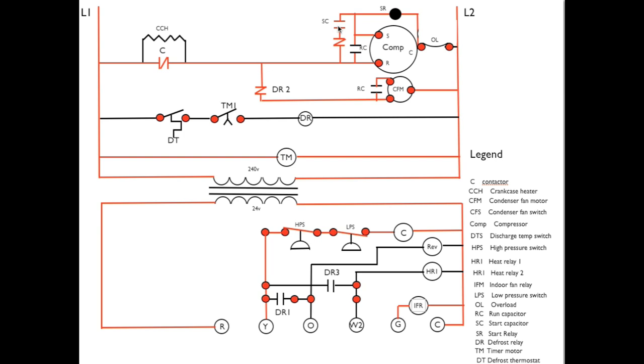Power flows through the normally closed contacts and energizes the compressor. Then power will pass to the normally closed DR2 contacts to energize CFM. The timer motor will be on all the time, and that's the sequence for first stage heat of the heat pump.